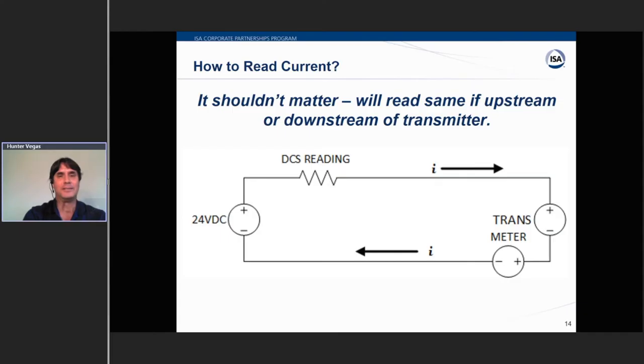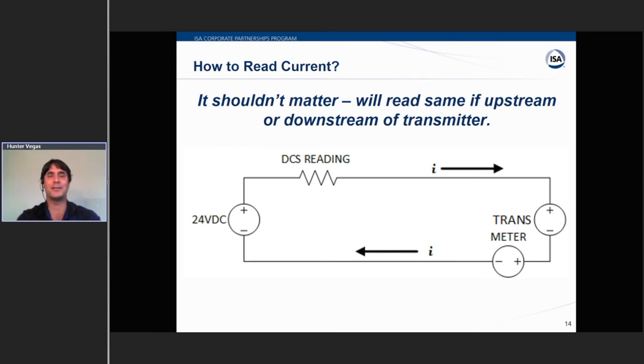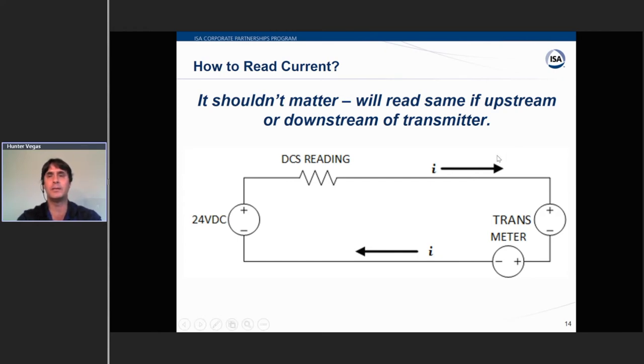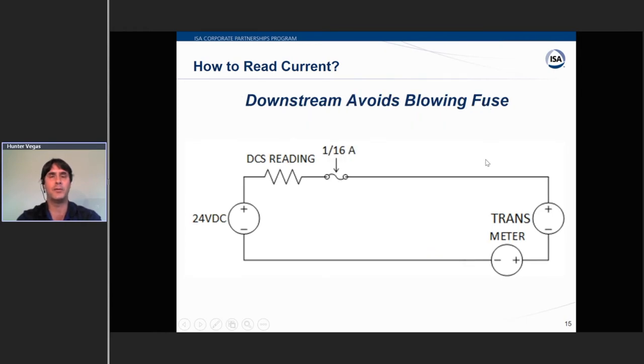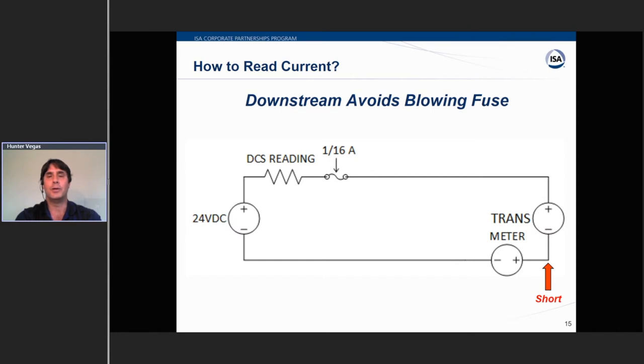The answer is: it depends. Technically it shouldn't matter, since the same current is going through the loop — you could put the meter anywhere and theoretically read the same. One reason to go downstream is to avoid blowing the fuse. If you get a short and drop a lead when hooking up your meter, and there's a sensitive fuse in the circuit, being downstream of the transmitter means the transmitter will only let 20 mA through, so the fuse is protected.